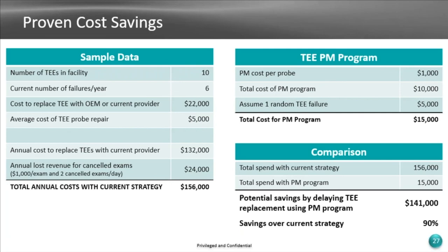So here's the cost of a TE program: $1,000 per probe. The total cost, if you're doing PMs on all 10 a year, is $10,000. We assume one random TEE failure, because they will fail. So your cost for the PM program is $15,000. You can see the cost savings here is 90% over your current strategy.